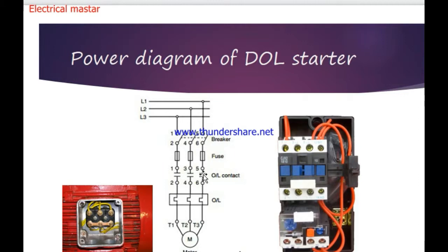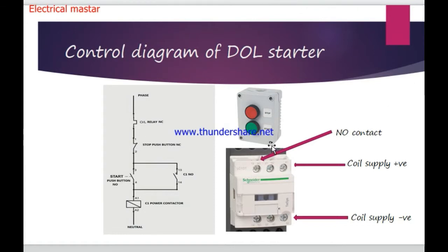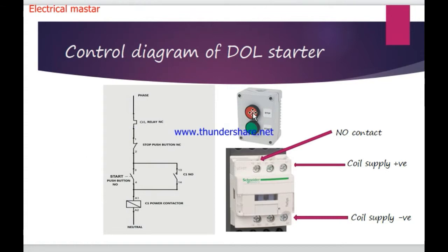The main control diagram: the control diagram of the DOL Starter handles on-off operation and protects against overload and short-circuit conditions. The main important components are the start-stop push button and magnetic contactor. If we start the motor, we press the start button; if we press the stop button, it will turn off. For protection, we connect to the overload relay so when the motor is overloaded, it will protect the motor from damage. That's why we use the DOL Starter.